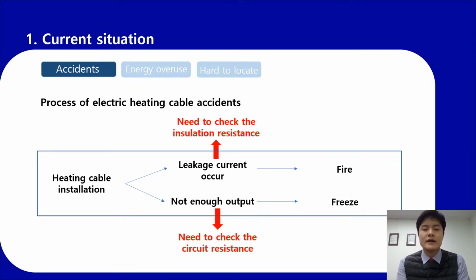And when there is not enough output, freezing happens in the pipeline. This accident occurs often on the site. After installation, the heating cable becomes aged while in operation. As a result, less output is made from the heating cable and the pipeline becomes frozen. As the output of the heating cable is closely related to its resistance value, a regular checkup of the circuit resistance is very important for freeze protection.